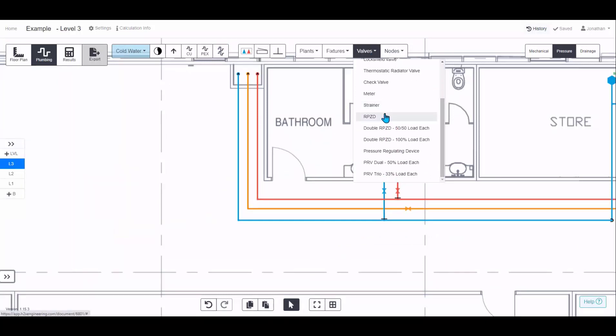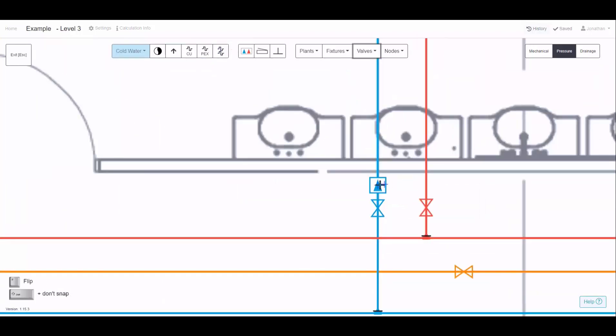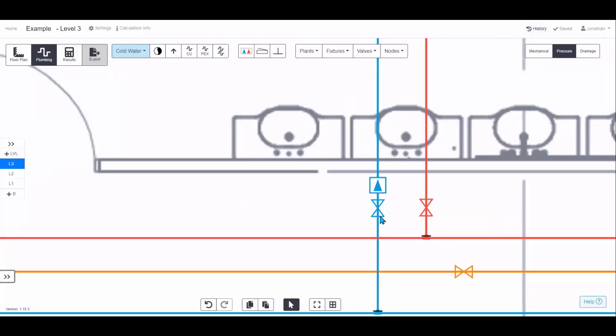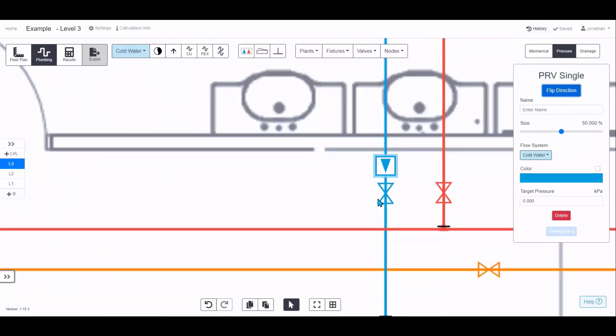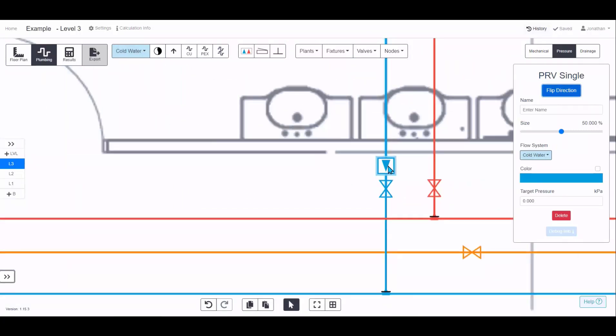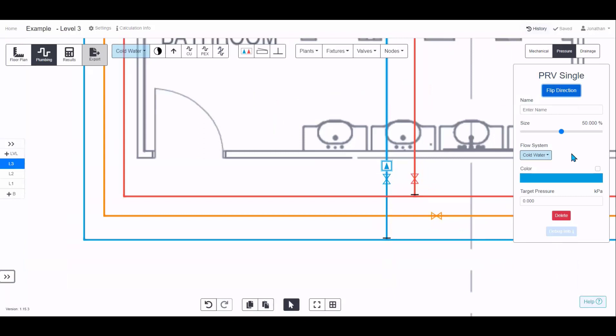Some valves like RPZ have significantly high pressure drops. The pressure regulating device is a special one — when you stamp it on the drawing, always make sure the arrows point in the direction of flow. If it's facing the wrong way it won't let water through, so flip it if needed and set the outlet pressure, for example 350 kPa.